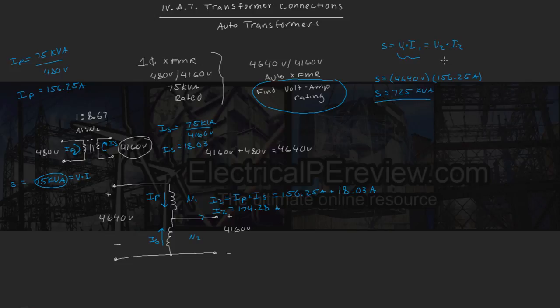Looks good so far. Let's try it on the secondary side. They should be identical. So on the secondary side, we've got an output voltage of 4160 that we're stepping down to from our new autotransformer, and an output current of I2, which we found right here by adding our two input currents to this node, IP and IS, which we found to be 174.28 amps. We check the math in our calculator and we come up with 725 kVA.